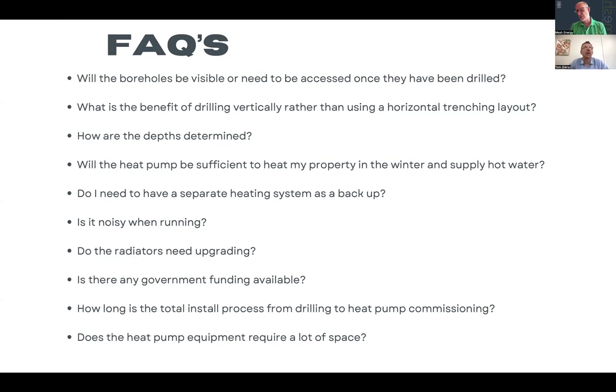So, Mario, similar questions really. What type of heating devices do you use in the apartments with ground source heat pump? It could be anything, couldn't it? So we have had clients who are using fan radiators, because they can then reduce the temperature of the system, which improves the efficiency.